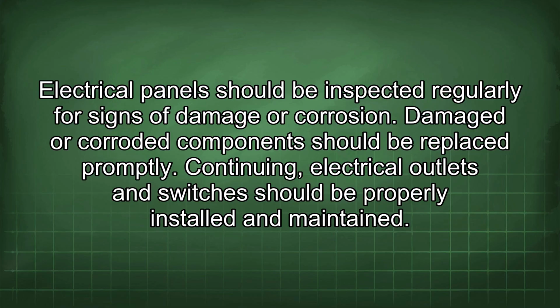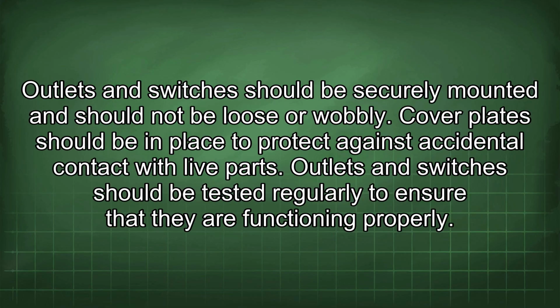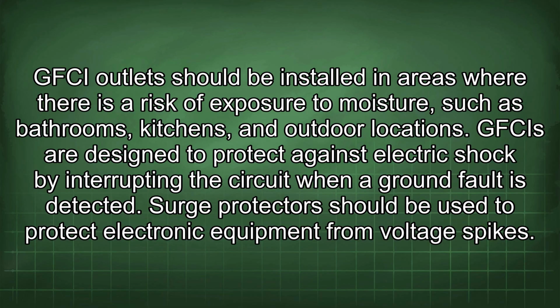Continuing, electrical outlets and switches should be properly installed and maintained. Outlets and switches should be securely mounted and should not be loose or wobbly. Cover plates should be in place to protect against accidental contact with live parts. Outlets and switches should be tested regularly to ensure that they are functioning properly. GFCI outlets should be installed in areas where there is a risk of exposure to moisture, such as bathrooms, kitchens, and outdoor locations. GFCIs are designed to protect against electric shock by interrupting the circuit when a ground fault is detected.